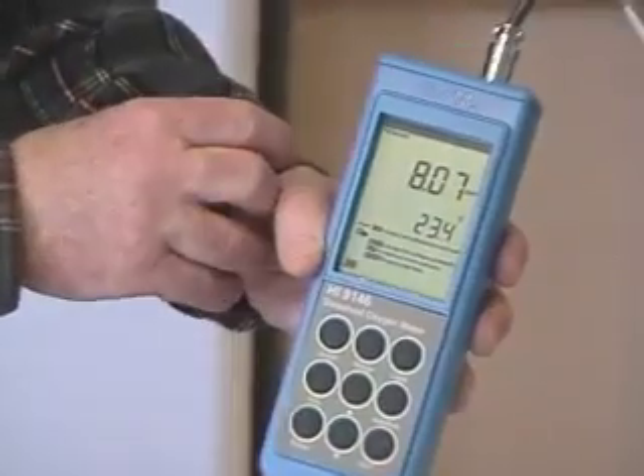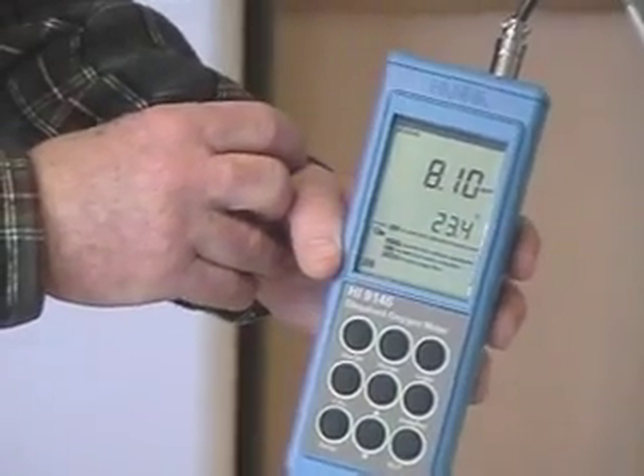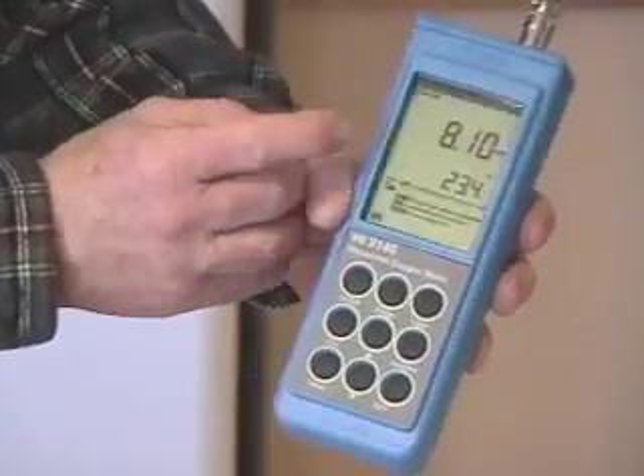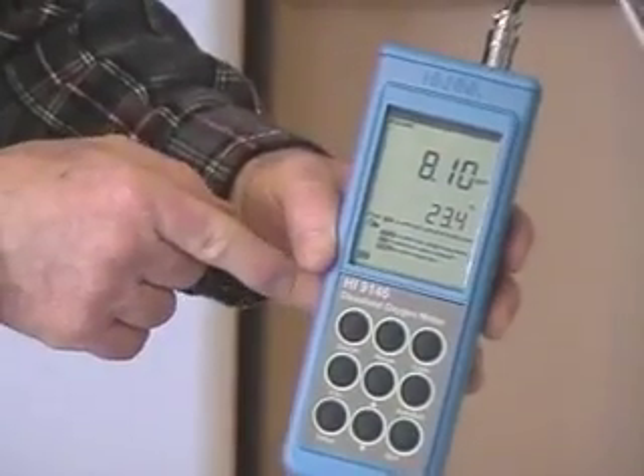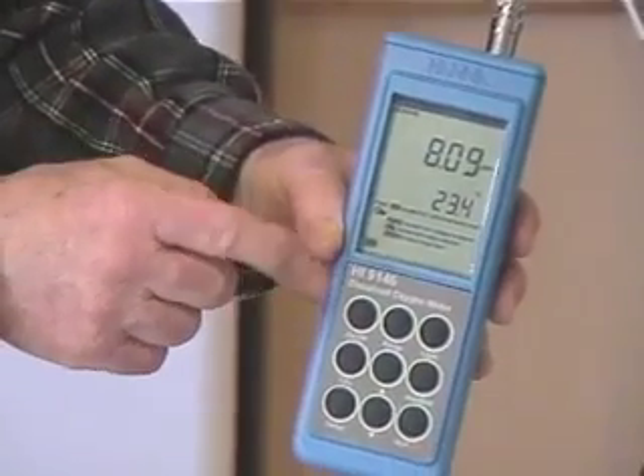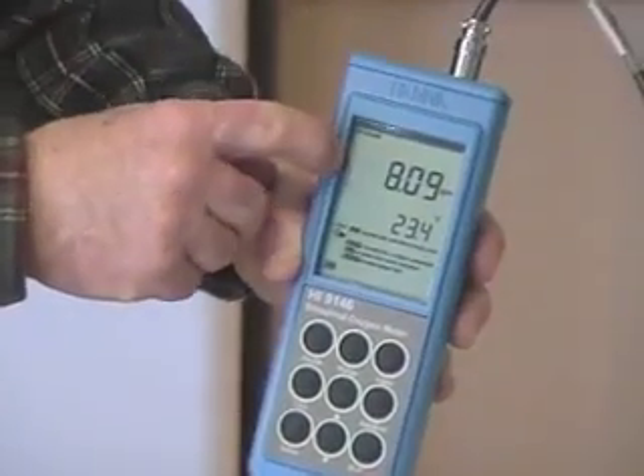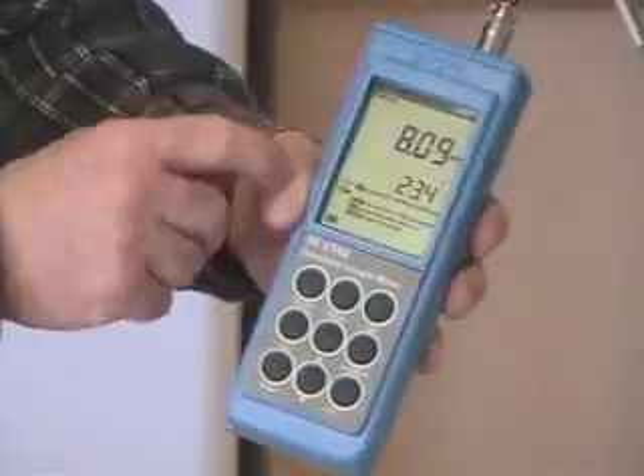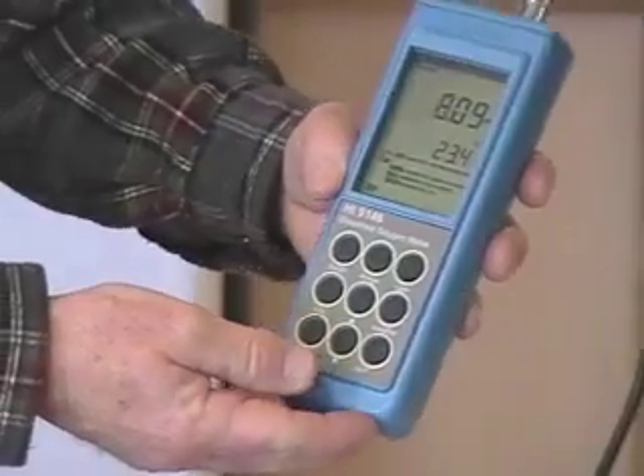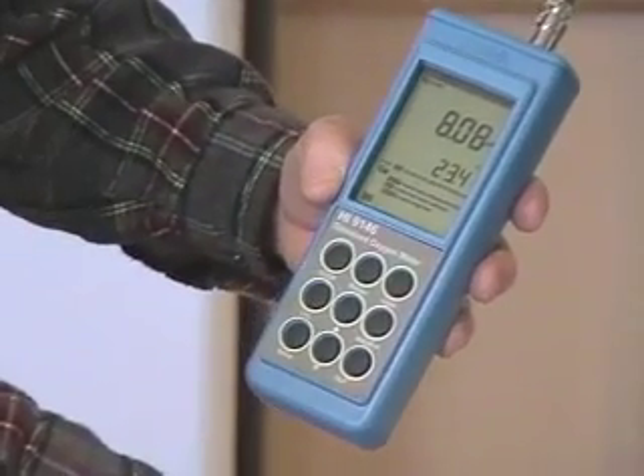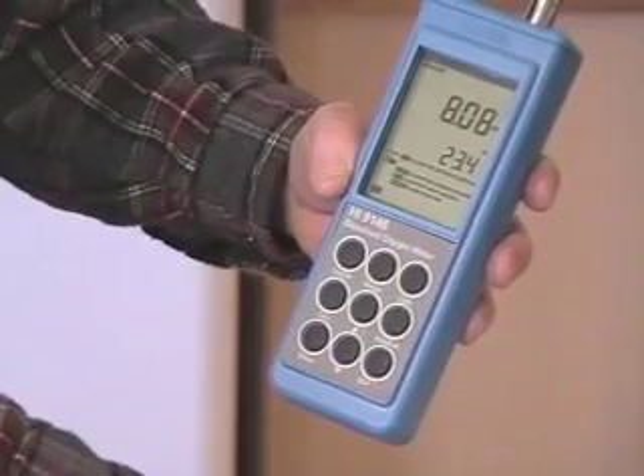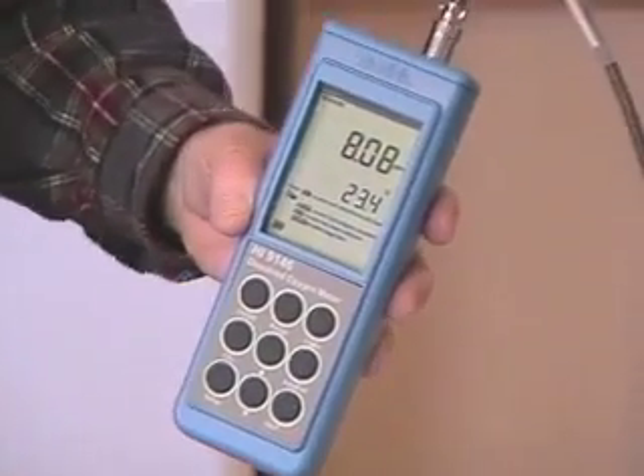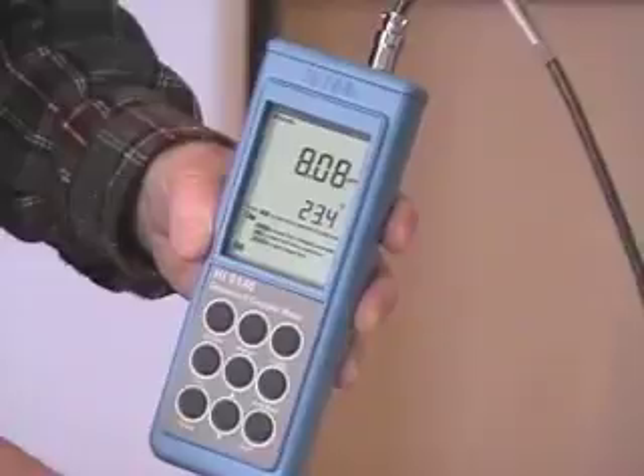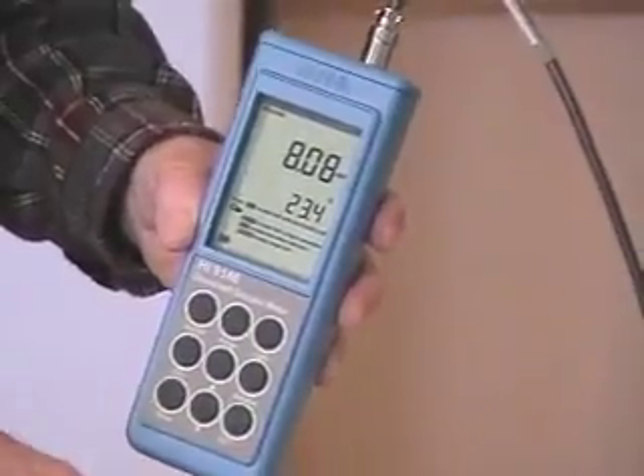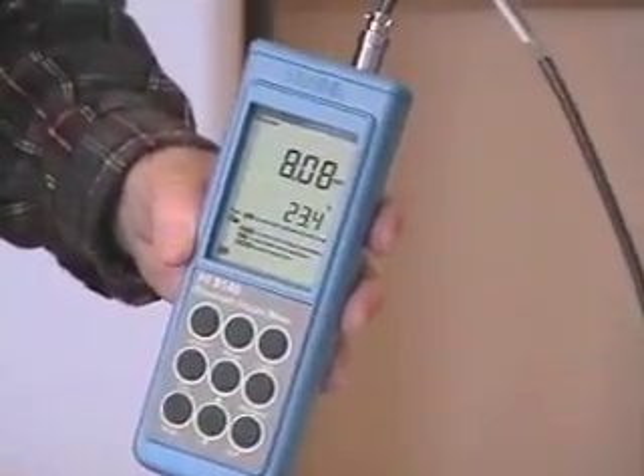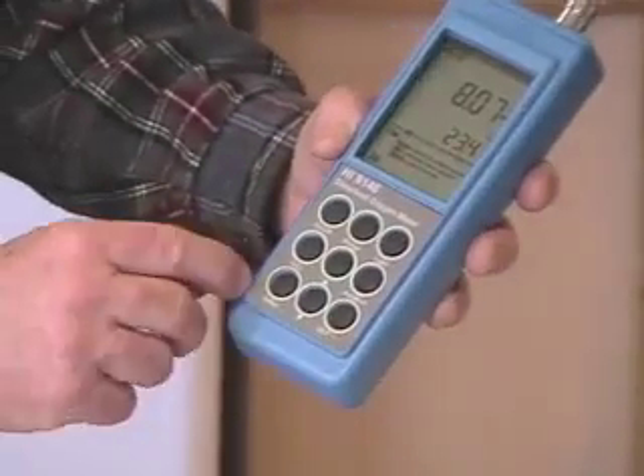And we go back to the dissolved oxygen and the temperature screen. I don't know if you noticed, prior to what we just did, when we changed the percent from 0 to 100%, the dissolved oxygen concentration was 14 point something. Now it's 8.09. That has decreased. Okay, the next step in calibration, we need to adjust 2 parameters that affect the calibration procedure. That would be salinity and altitude. So we're going into setup.